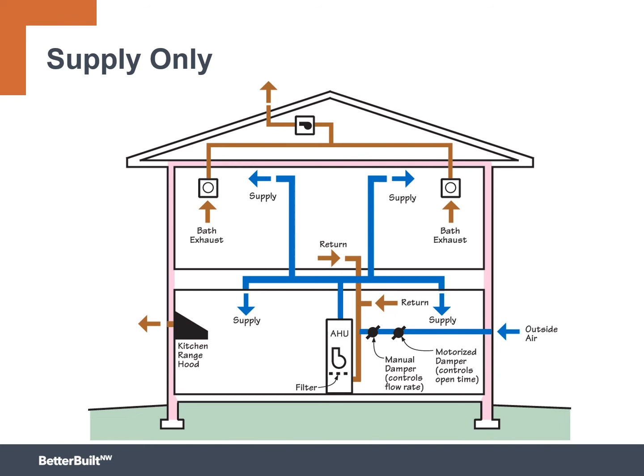So one of the challenges with supply side ventilation, I'm going to go through some animations here, right? So we have supply air coming in to the return side, pushing air in. This actually positively pressurizes the house, right? So you're actually forcing air out through every gap and crack, as opposed to the exhaust fan, which sucked air in through every gap and crack. This one forces air out through every gap and crack. And imagine what happens if you push warm, sort of moist air from the main body of the house into an attic when it's 40 degrees outside, or into a wall on the north side of the building that never gets sun. That potentially can be problematic.